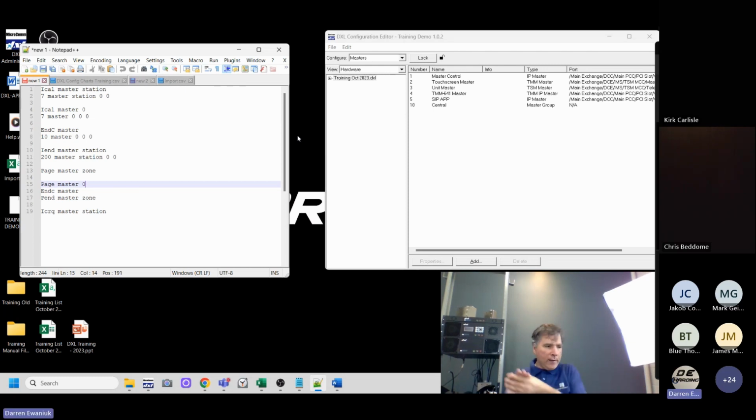So both sending a command to the intercom system to, for example, make an intercom call, within the intercom system there'd be a block of 5 numbers that we would write. The first number would be the command, the second number would be the master station in the case of a call request, the third number would be the intercom number. Likewise, when intercom sends you a response back, it'll send you a response as a block of 5 numbers, a command, and then up to 4 parameters.